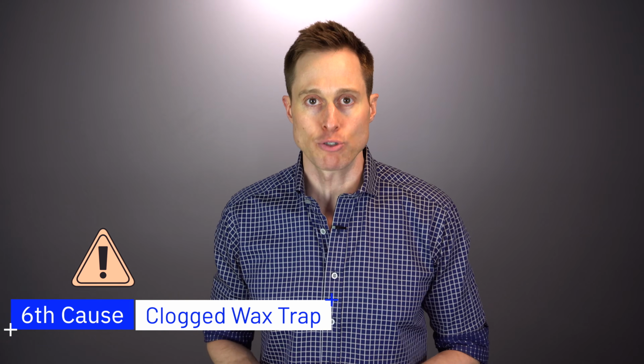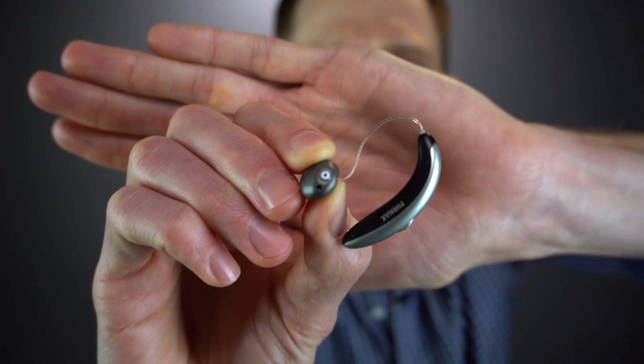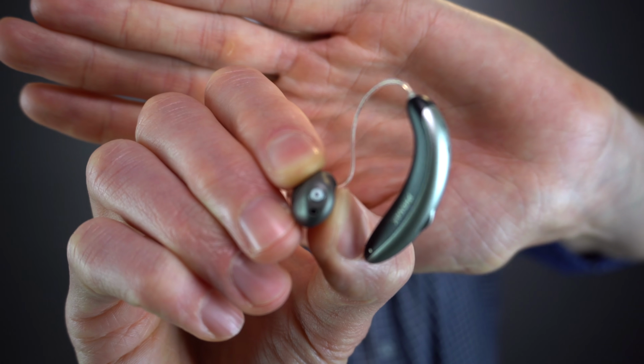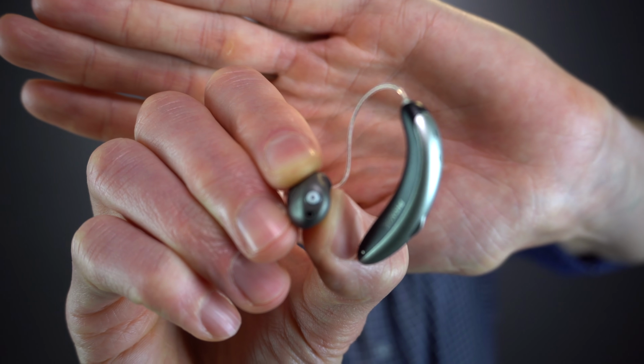And the sixth and possibly the most common reason why your hearing aids will stop working is a clogged wax trap. Hearing aid wax traps cover the tips of your receiver. You can see it right there, that little white tip. If that gets plugged up with earwax, it ends up blocking the sound trying to make its way into your ear. These wax traps are needed because they prevent earwax from getting into the electronic components inside of the receiver. The problem is that these get clogged all the time, and chances are if your hearing aid stops working, this is the first thing that you should be looking for.